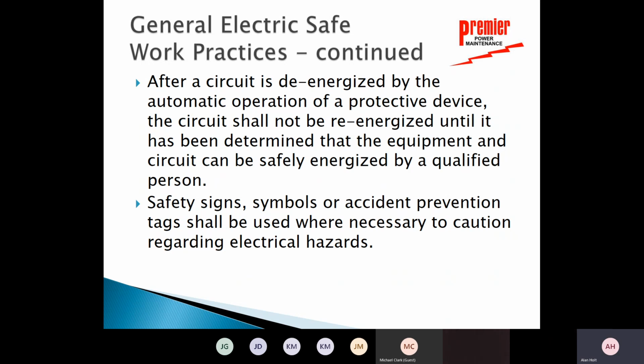Now, some other safe work practices that Marathon specifically points out. After a circuit's de-energized, and by being de-energized in this part of the process means that a protective device, a protective relay, a trip unit on a 480-volt breaker, something has caused that to be de-energized. So it's tripped offline, okay? That shall not be re-energized until it's been determined that all the equipment in that circuit can be safely energized. Okay, so basically a cause has to be found when something trips off. They don't want it just to be re-energized.